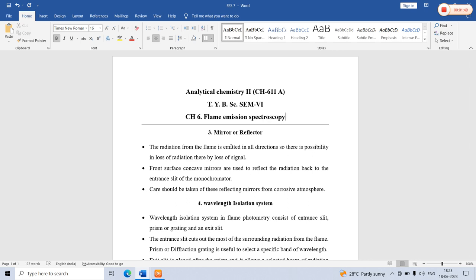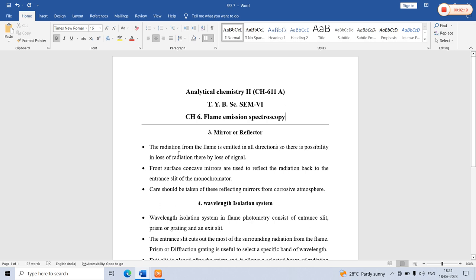After the flame, a mirror or reflector is placed. The role of the mirror or reflector is as follows: the radiation from the flame is emitted in all directions, so there is a possibility of loss of radiation and thereby loss of signal. The neutral atoms get excited in the flame and emit wavelengths in the form of radiation. If radiation loss takes place, it will cause the loss of signal.